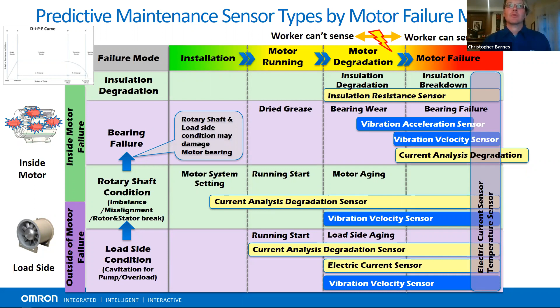So if we look at the vibration sensors first, they'll help you pick up those failure modes. As you can imagine, as the wear happens and the machine starts to fail, the vibration is going to get worse and worse. You've probably experienced this at home, whether it's the fan on your air conditioner, your fridge, or something else. It gets noisier and noisier as it starts to fail, and it reaches the point of the wavelengths where you can hear it as a human, but the vibrations start out quite small. If we can catch them with a sensor earlier, you can catch them before you hit a failure, which is the goal of predictive maintenance, really: catching the stuff early on.